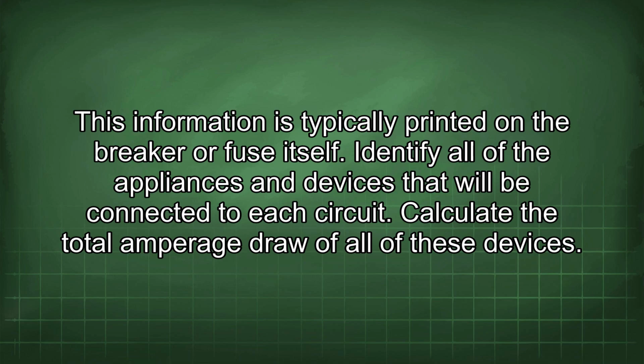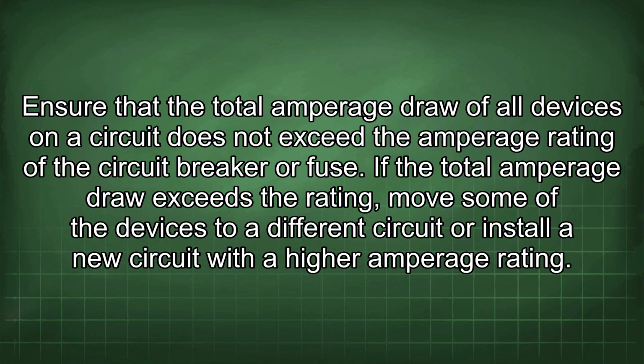Identify all of the appliances and devices that will be connected to each circuit. Calculate the total amperage draw of all of these devices. Ensure that the total amperage draw of all devices on a circuit does not exceed the amperage rating of the circuit breaker or fuse. If the total amperage draw exceeds the rating, move some of the devices to a different circuit or install a new circuit with a higher amperage rating.